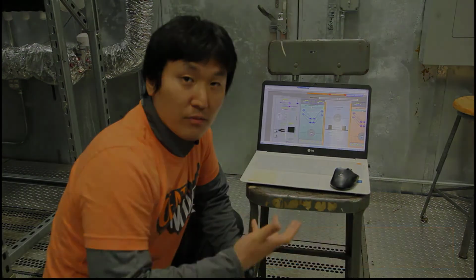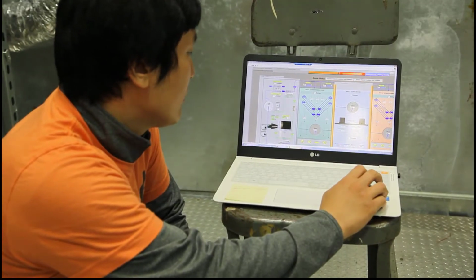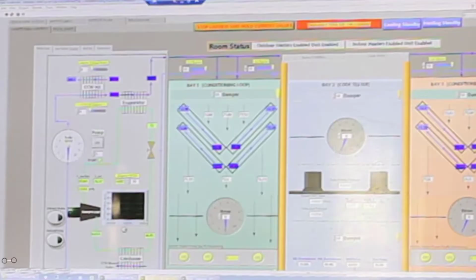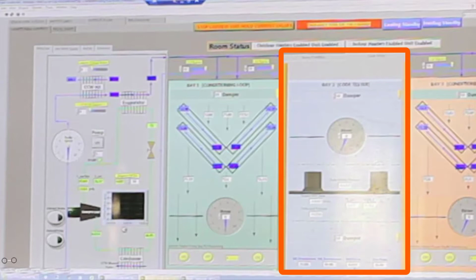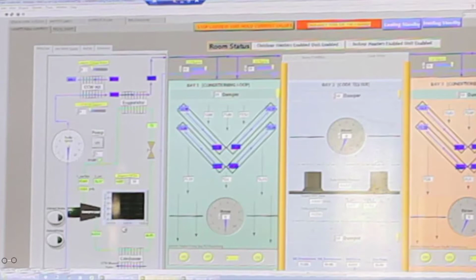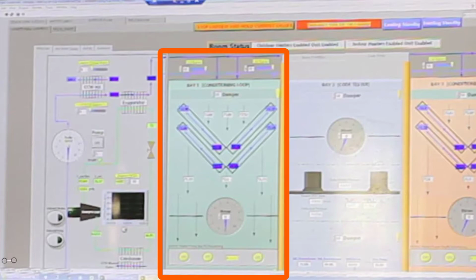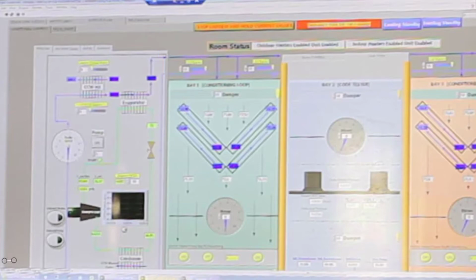Let me briefly explain. This is the LabVIEW controller. So we have a nozzle box and blower, so we can control the airflow rate, and then we have a cooling coil, so we can control the cooling water flow rate and also the temperature. Then we have a heater, and then we have a humidifier, so we can control the humidity and the temperature at the same time.